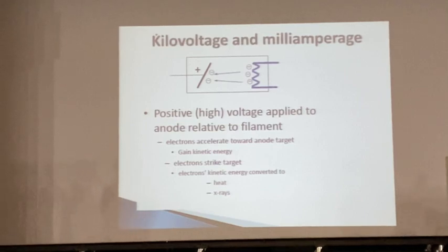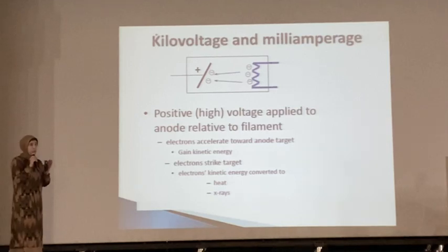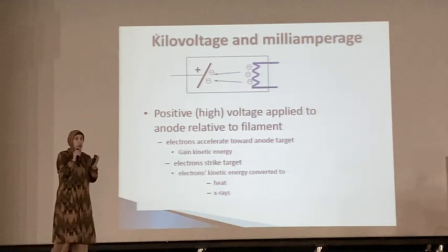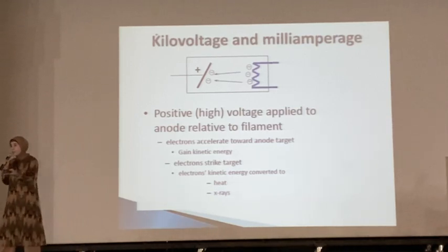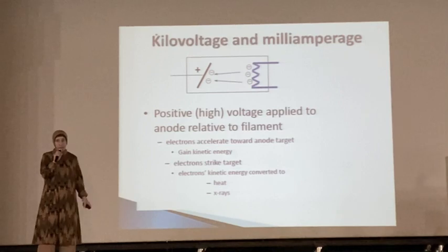This is why it is used, because of its high melting point. The melting point should be high because, by the process of thermionic emission, we have to increase the temperature of the cathode to about 2000 and more degrees centigrade. Then the electrons are accelerated toward the anode. Inside the anode, there will be interaction with the anode and formation of heat and the X-ray.